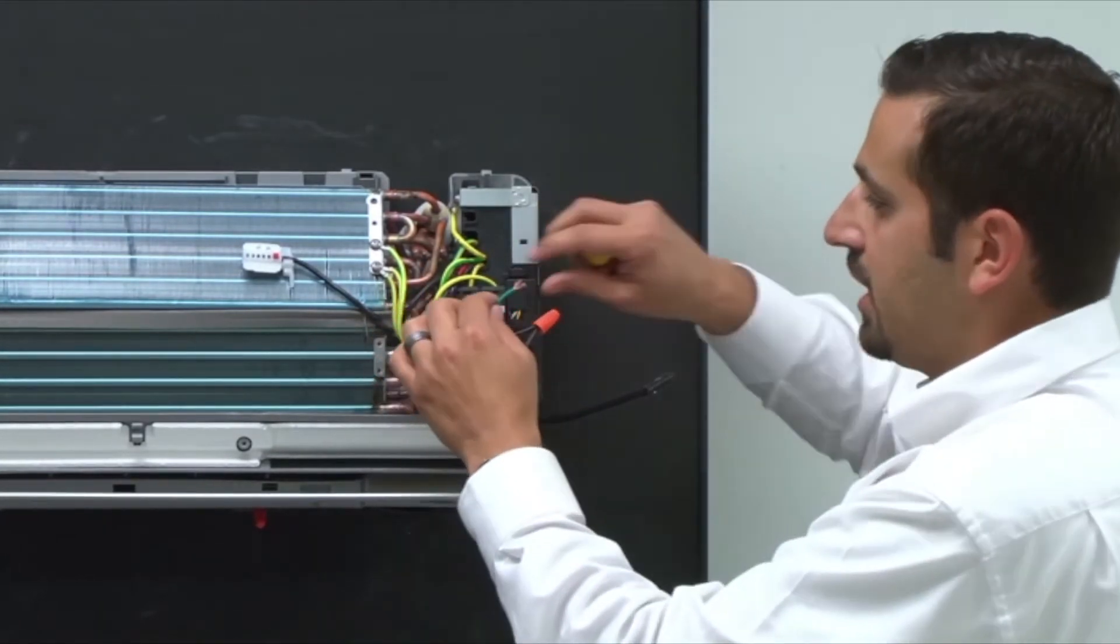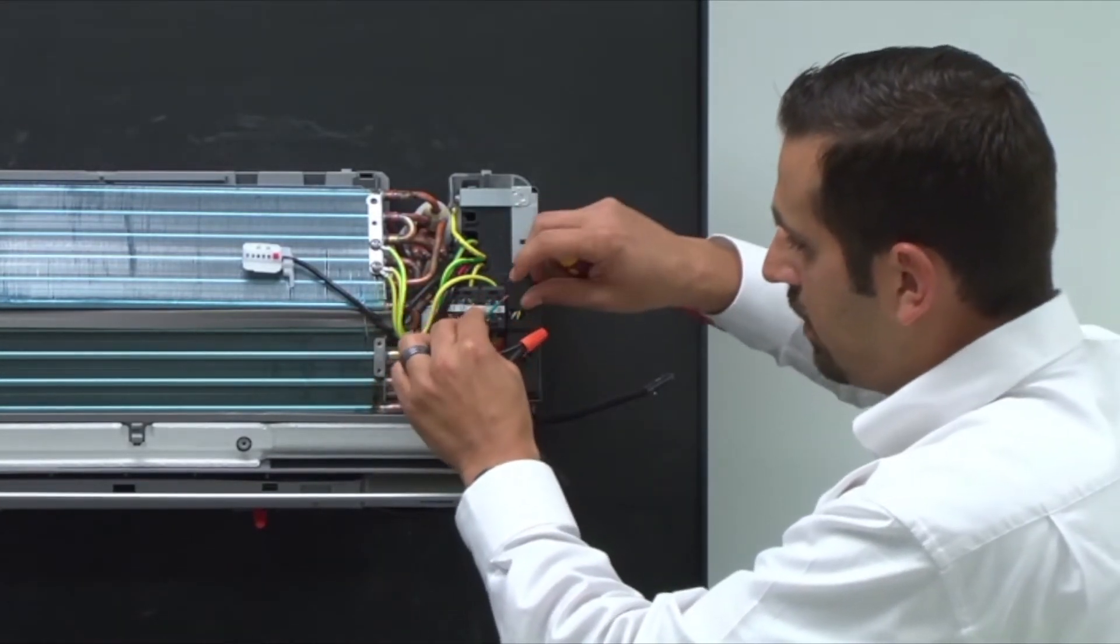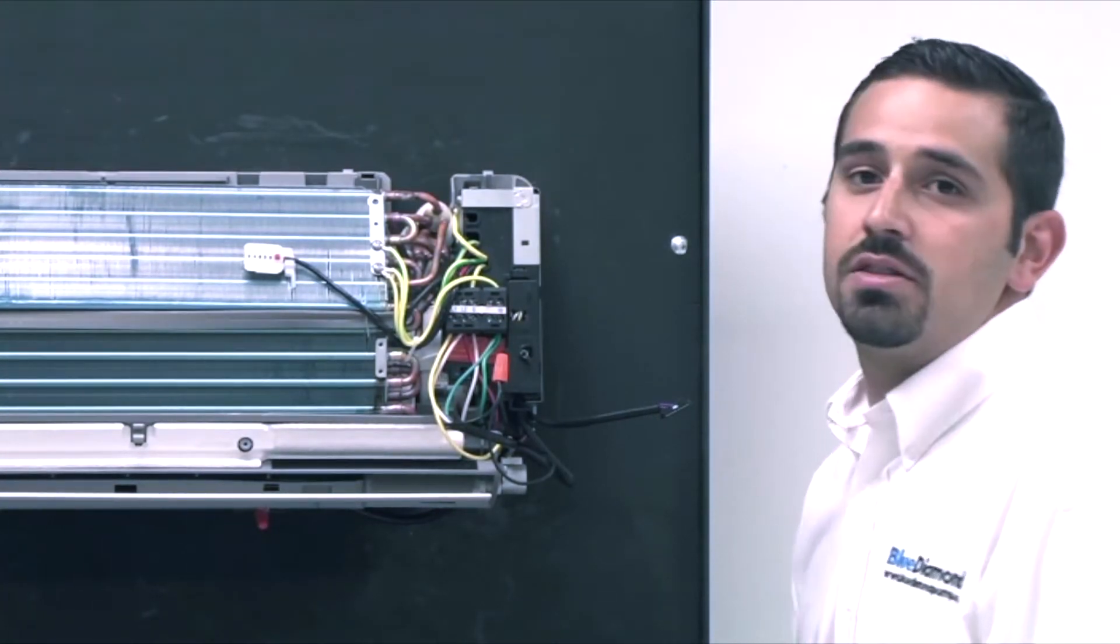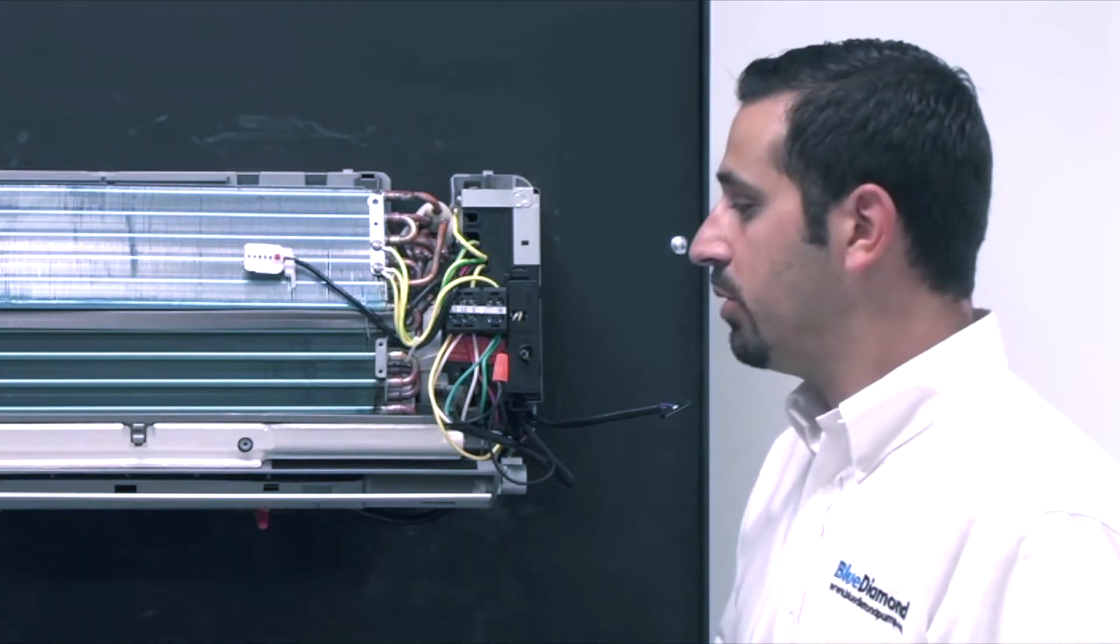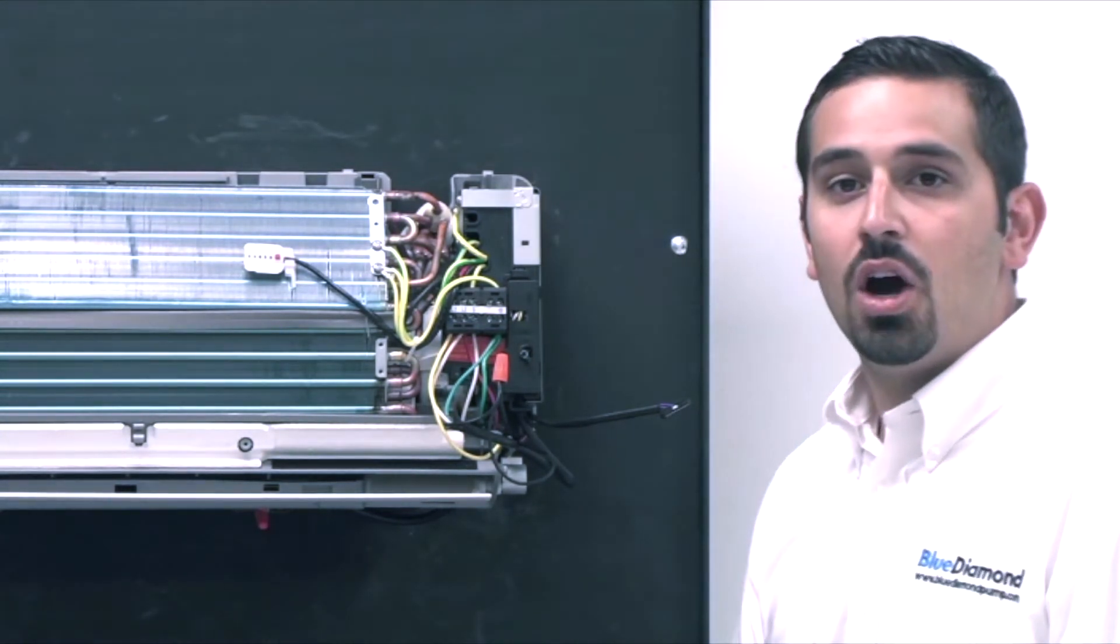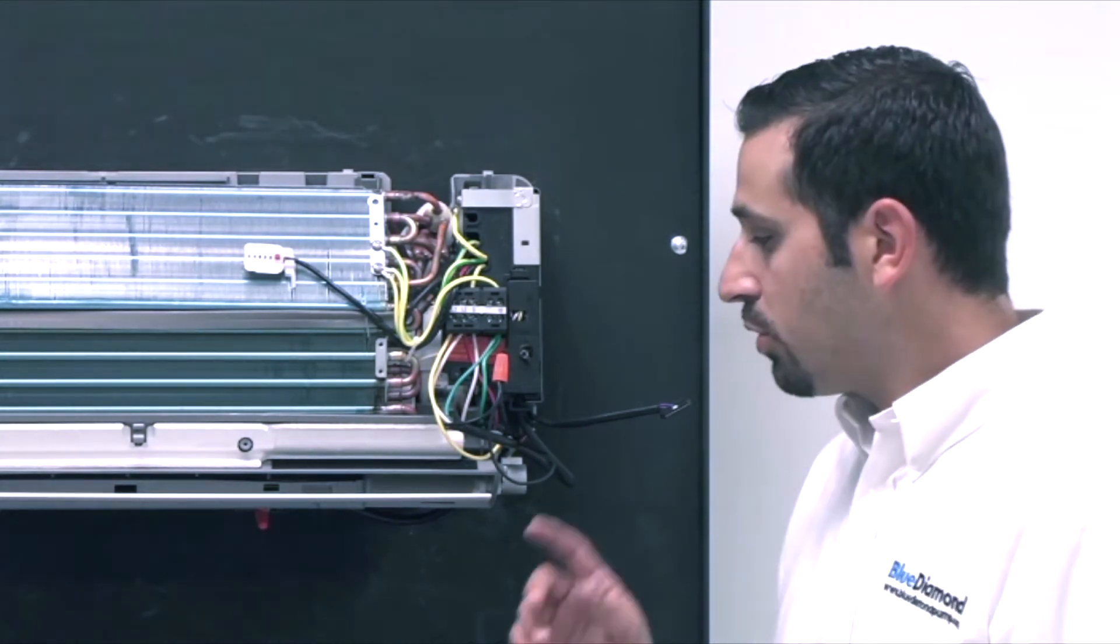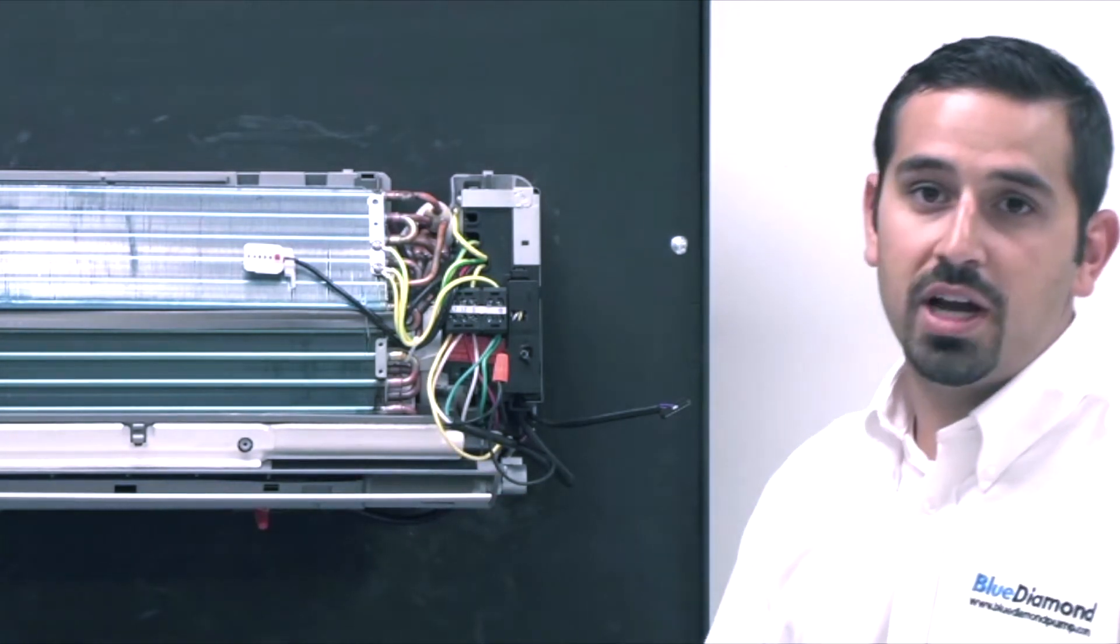Lastly, we will take the green and that will be our ground. We just want to make sure that everyone understands that we are not running L2 or S through the pump. The only thing we will break with the Blue Diamond pumps is your L1. L1 will run through the pump. Use our normally closed contact to bring the voltage back to your air handler.